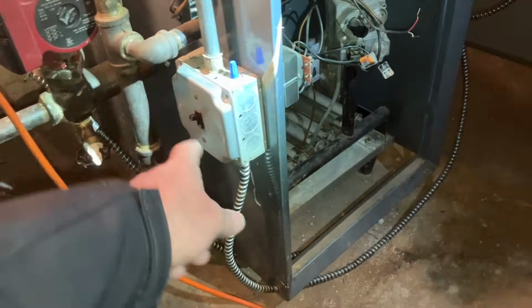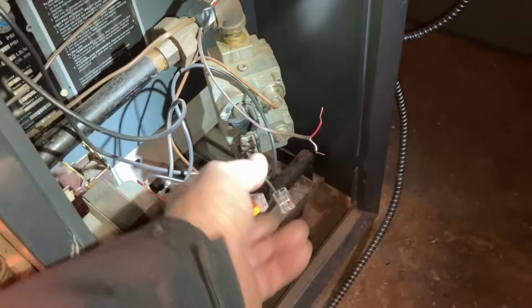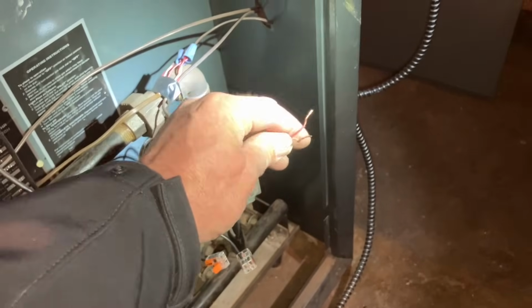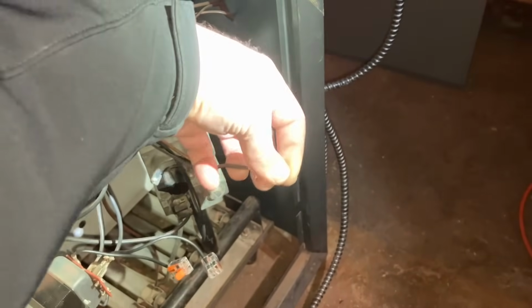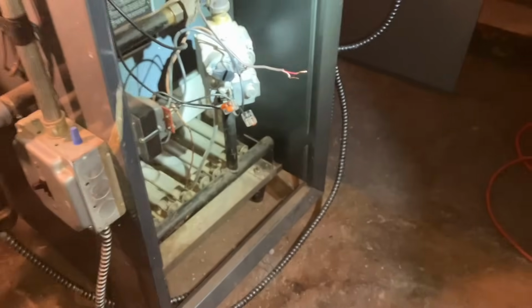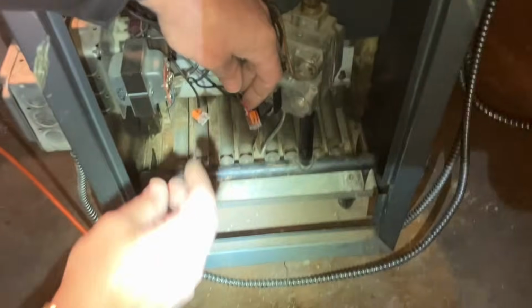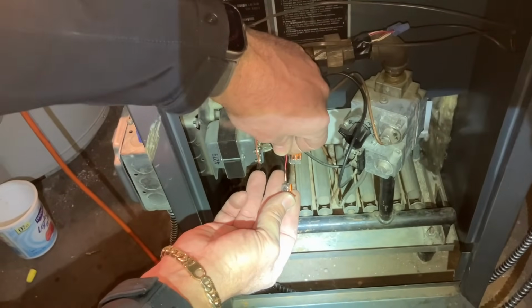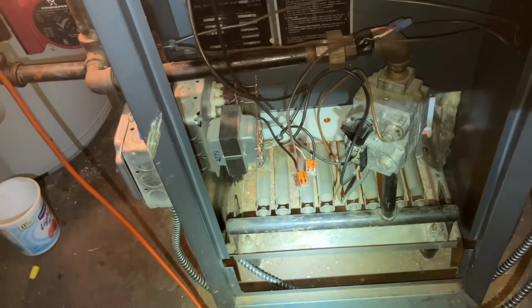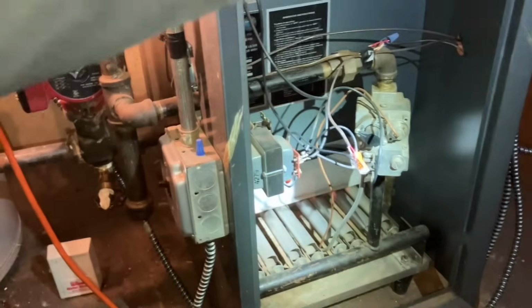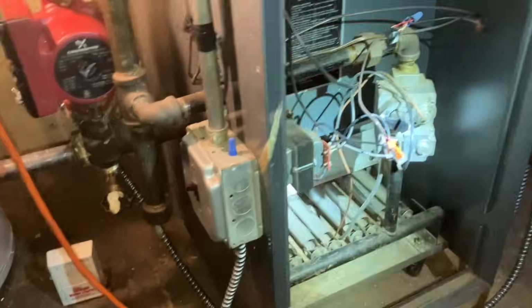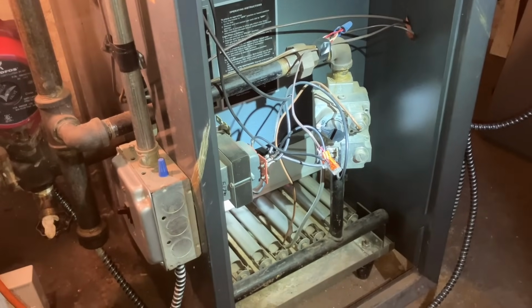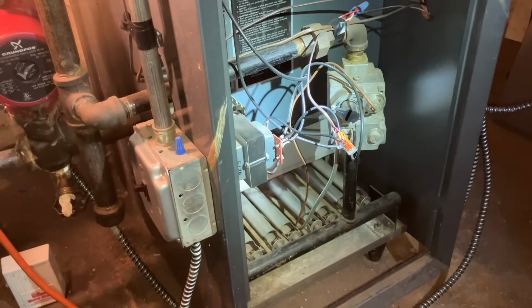So right now I have the power on. Yeah, this was that TT connection, and this is coming from your relay, right, which will turn the boiler on, the end switch. Okay, so let's put this together. Do you want to hold that for a split second? Because I like to feed people education. So if I put this in there, we have ignition. And if you were to turn off the thermostat upstairs, that will turn this relay off, and the boiler should turn off. So right now the boiler's running. Good. It can't run immediately, which I can see, obviously.